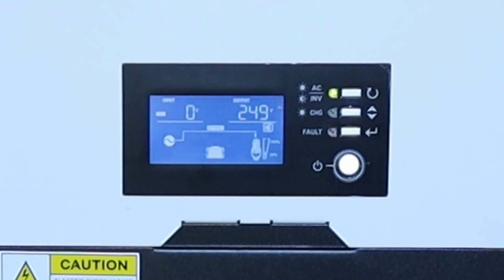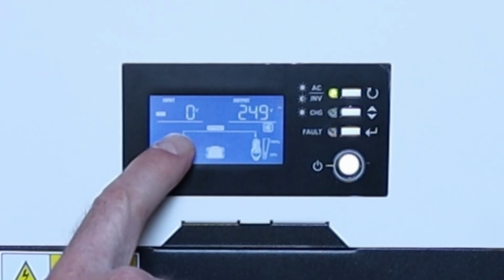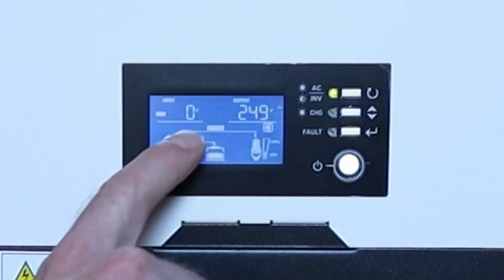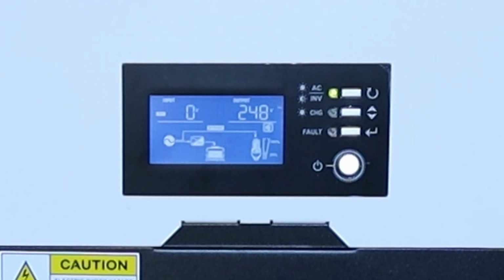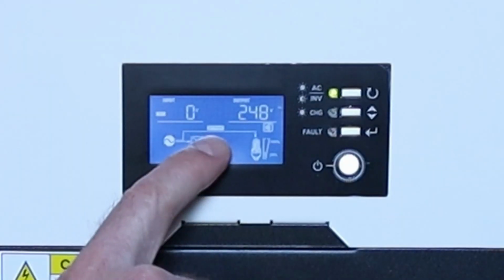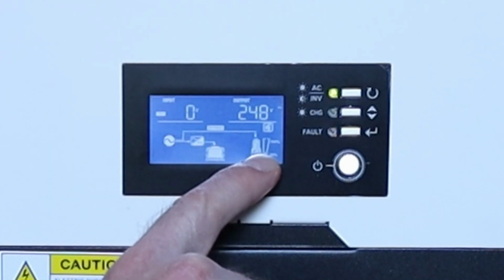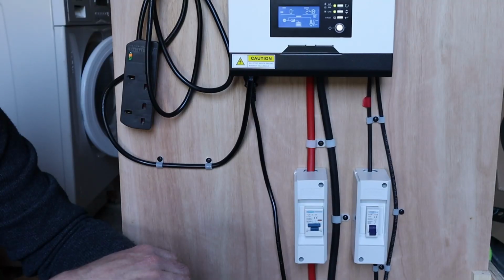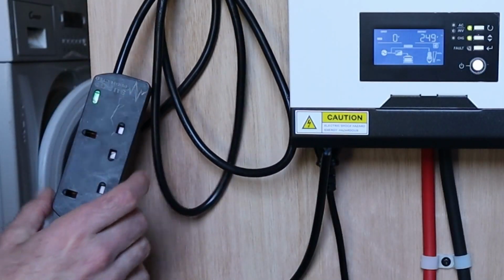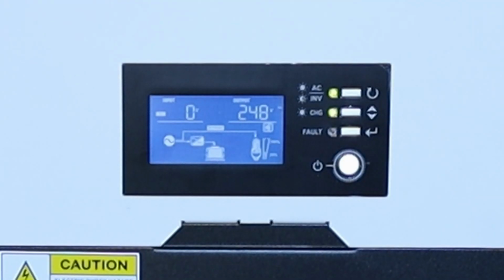You heard a little click there - that's the automatic transfer switch, which uses that from the mains and switches it into what's called bypass mode straight to the load. But now it's actually reconnected to the battery. So the mains supply at the moment is charging the battery and also going straight out to the load, which at the moment we haven't got anything on, even though the inverter's switched on. So that's connecting utility power.